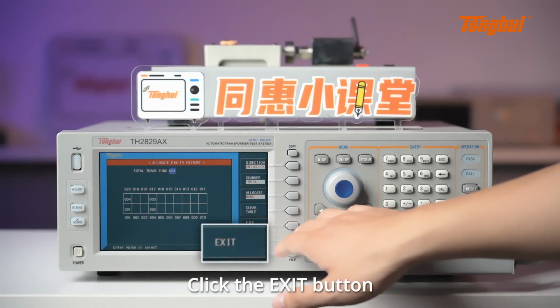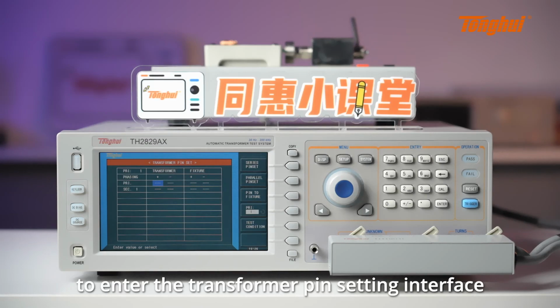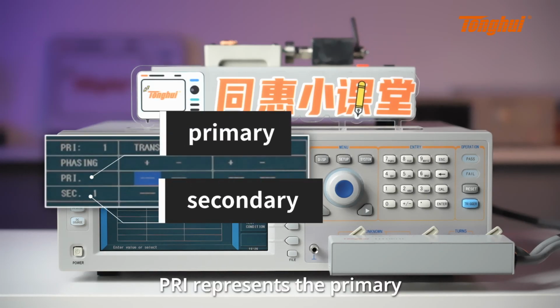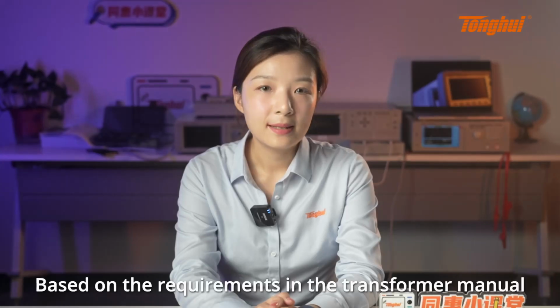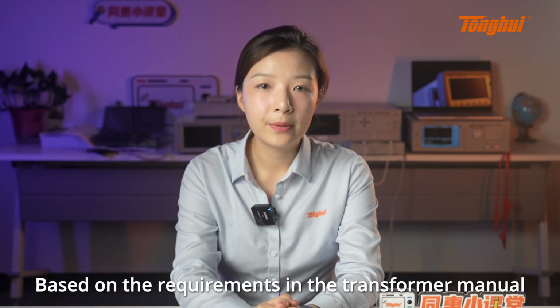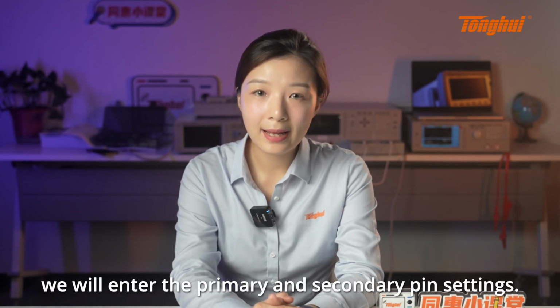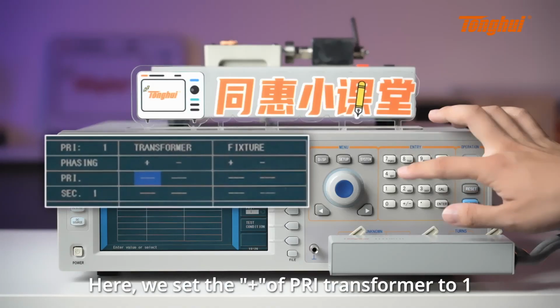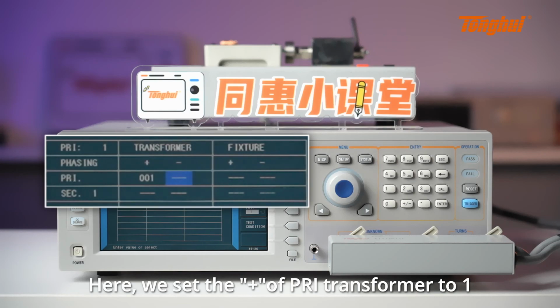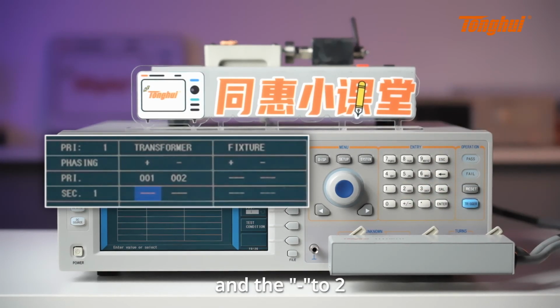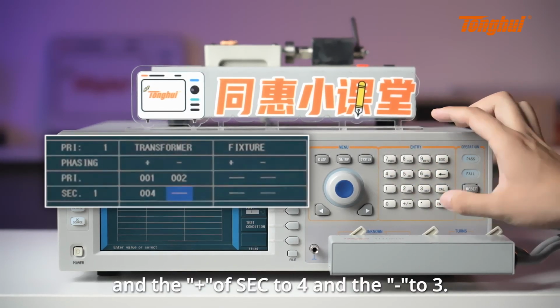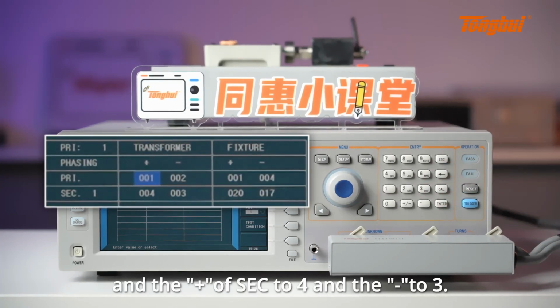Click the Exit button to enter the transformer pin setting interface. PRI represents the primary and SEC represents the secondary. Based on the requirements in the transformer manual, we will enter the primary and secondary pin settings. Here we set the plus of primary transformer to 1 and minus to 2, and the plus of secondary to 4 and the minus to 3.